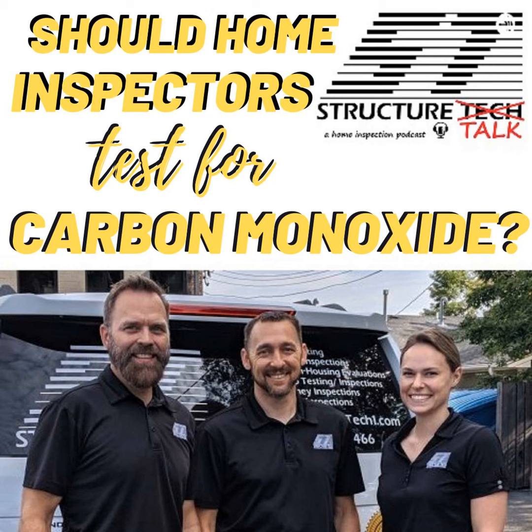If you ever do a CO test on, say, a power vent water heater, and you're testing for just raw CO, the number is always going to be really low because you've got this draft fan at the top of the water heater that pulls in a ton of household air. A large percentage of the air coming out of that exhaust terminal is going to be household air, and it's going to be very diluted. And so your CO level is going to be very low.